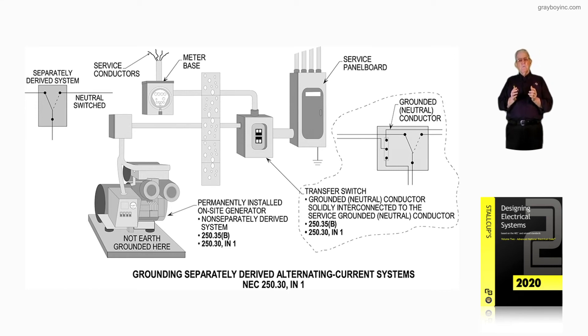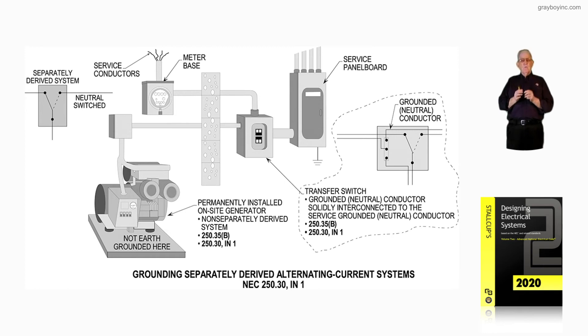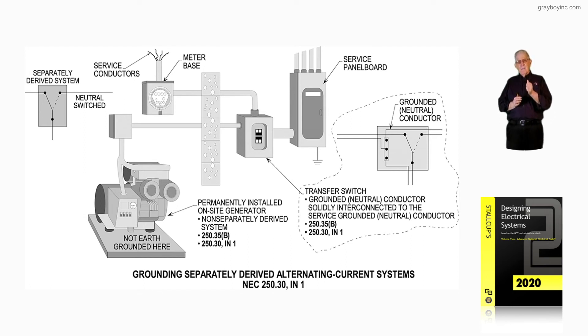If it's an optional standby generator, you can bring it on automatically or manually, you can design it for the loads that you want it to supply, you could have load management with it, or you could just feed all the loads at one time. So if it's an optional standby generator under 702.2 informational note, you have a lot of privileges there. The owner can tell you as the designer what they want to supply, and you can provide it.